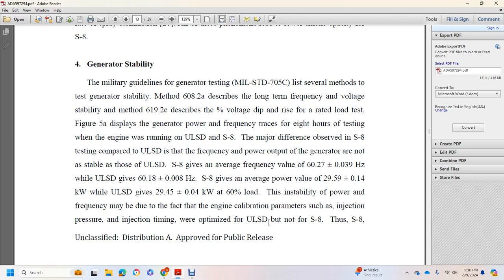Figure 5A displays the generator power and frequency trace for the 8-hour testing when the engine was running with ultra-low sulfur diesel and S8. The major difference observed with the S8 testing compared with the ultra-low sulfur diesel was that the frequency and power output of the generator were not as stable. S8 gave an average frequency of 60.27 plus or minus 0.039 hertz, while the ultra-low sulfur had 60.18 plus or minus 0.008 hertz.